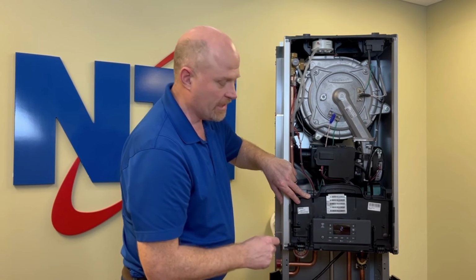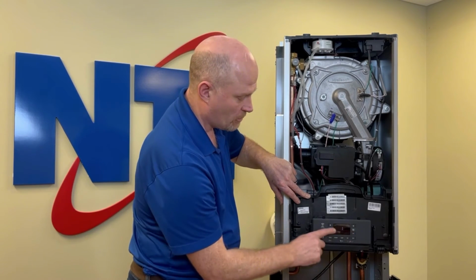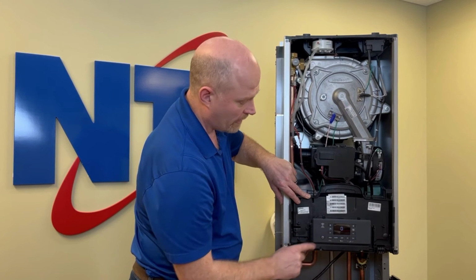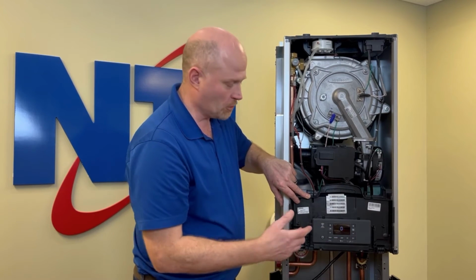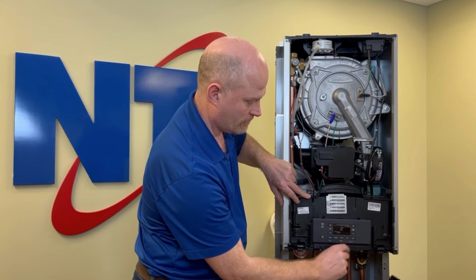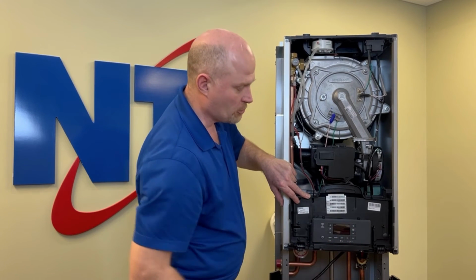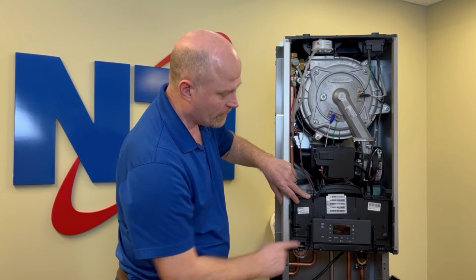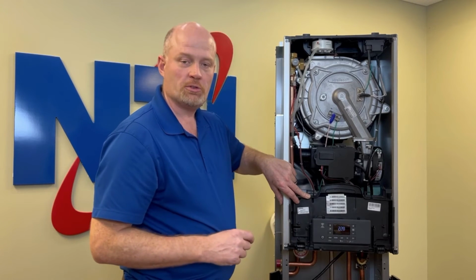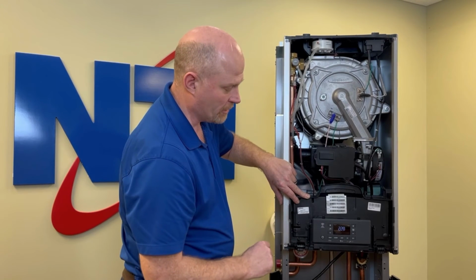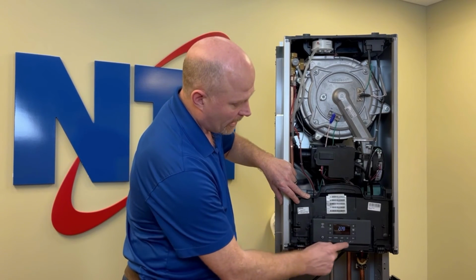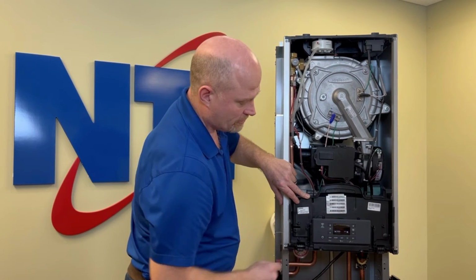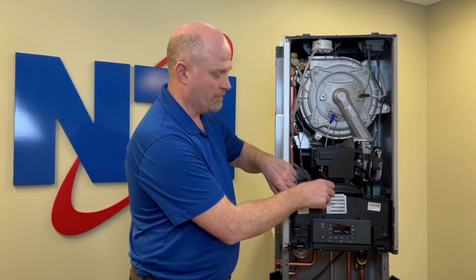Number 2 indicates an aquastat, number 1 is for a tank sensor, and 0 is for a combination or combi boiler. Make sure you press OK to save your setting. When the display goes blank or shows you dashed lines, it's saving or updating your settings. Don't worry about that. And now you've fixed the error code 203.